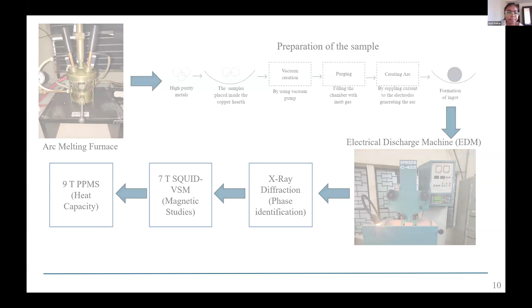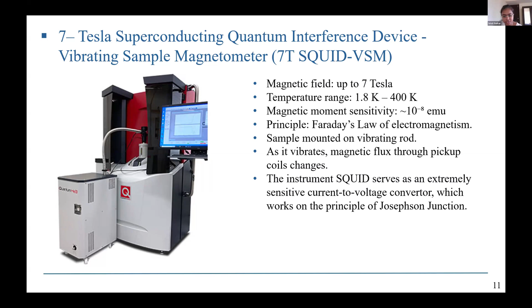This system works on the principle of Faraday's law of electromagnetism. The sample is first mounted on a vibrating rod. After loading the vibrating rod inside the system, as it vibrates, the magnetic flux through the pickup coil changes. The SQUID serves as a sensitive current to voltage converter, which works on the principle of the Josephson junction.